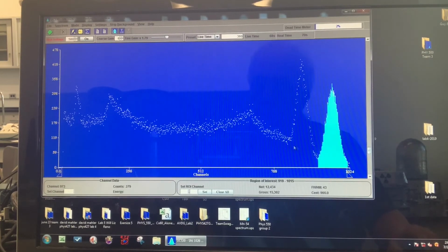And you will then keep these gain settings and then put all of your sources, or at least 4 or 5 of them. We'll have 2 high energy peaks here. We'll have the cesium-137, which is at 662, and we can put in a low energy gamma down here. And then we will have a full range of energies, and we can plot the R value for energies as low as 88 keV up to 1.3 MeV.